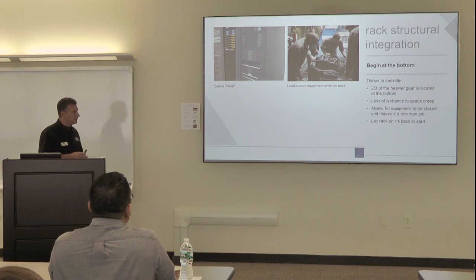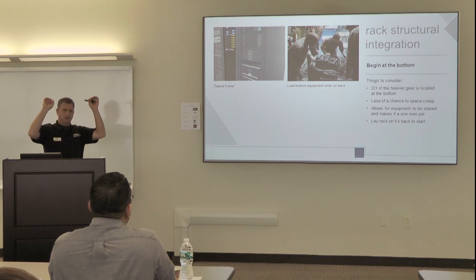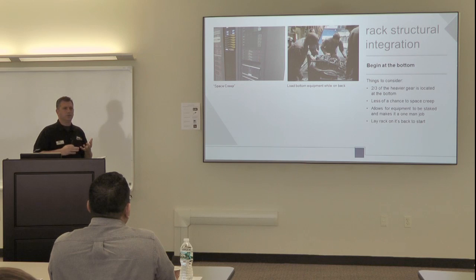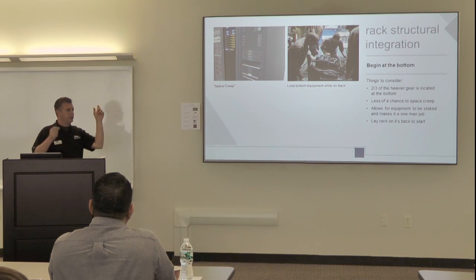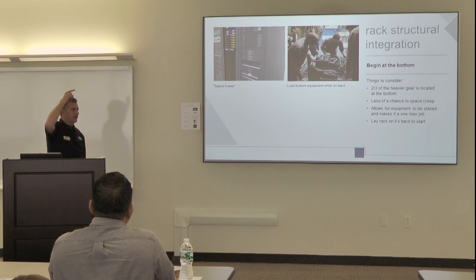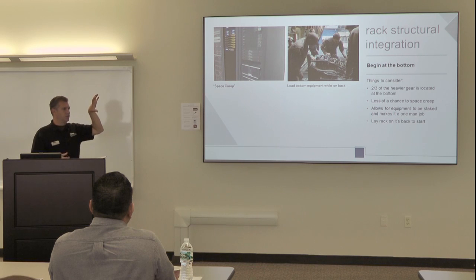Space creep is another issue. EIA standards have a very tight tolerance on where the holes are, but every panel and piece of gear has big ob-rounds on them. So if you're justified too low or too high when you put the rack screw in, by the time you get to the top, even though you may supposedly have two rack spaces, it may come up short because of tolerance that built up. You'll get to the top and find it doesn't fit, and then you have to start from the first screw at the bottom, loosen everything, and hopefully drop it down to get it in.